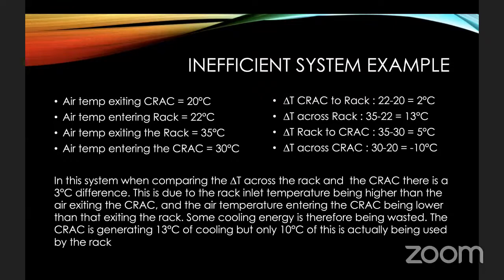So in this example, we have the air exiting the CRAC at 20 degrees. We have the air entering the rack at 22 degrees. We have the air exiting the rack at 35. And then we have the air entering the CRAC at 30. This means our delta T from the CRAC to the rack is no longer 0. It is now 2 degrees. So I have lost 2 degrees of cooling. Where have I lost it? We don't know. But somewhere between leaving the CRAC and reaching the rack, I've lost 2 degrees of cooling energy.